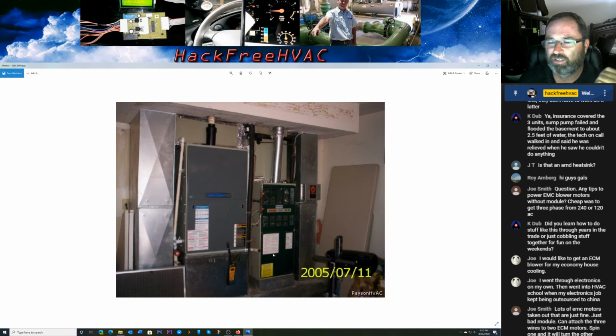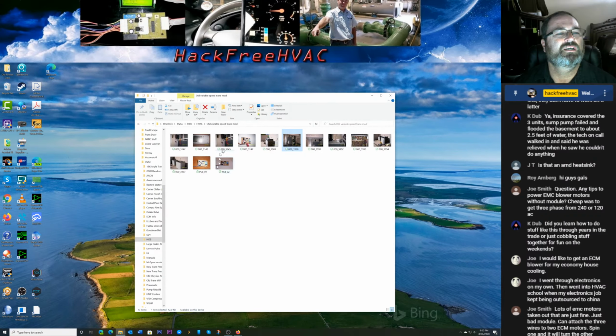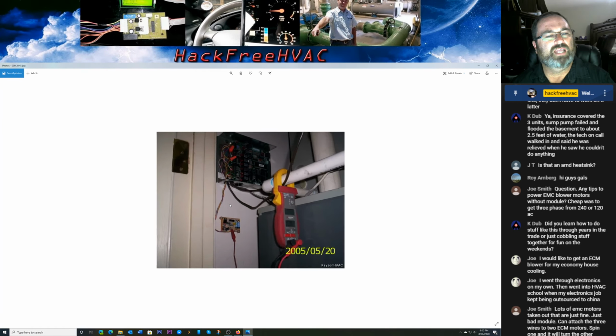And so did the compressor. Yes, Joe, way ahead of its time. And they changed it out to this one and just hooked up a couple wires so the fan would just run on the green wire off of the interface, and then left, and it never worked right and froze up and everything. Well, because this had an intermediate controller up here that everything tied to.